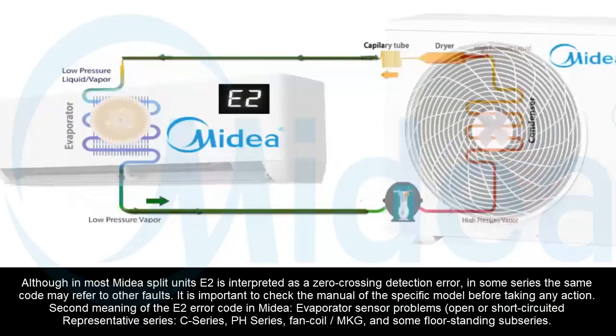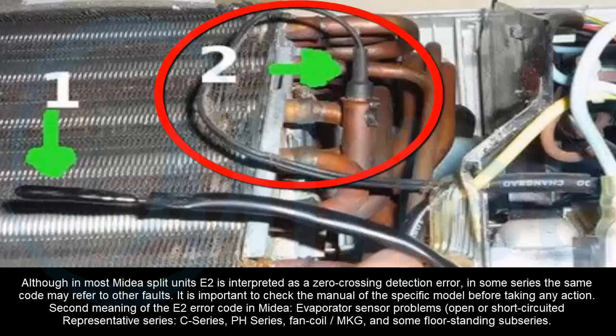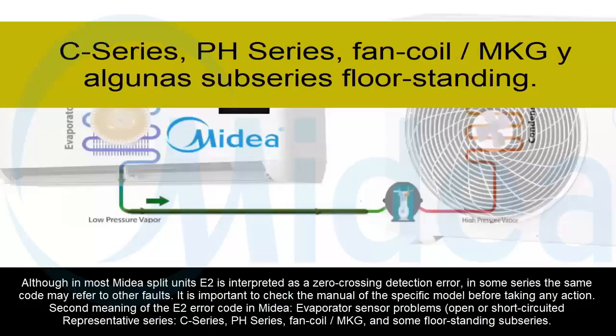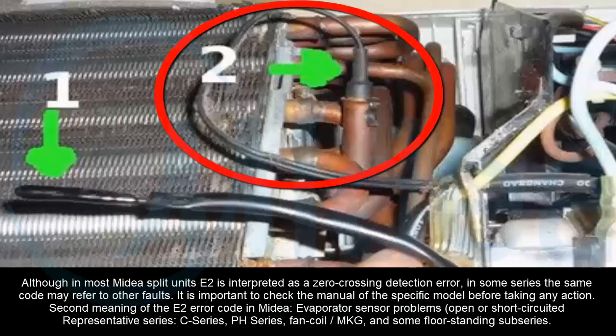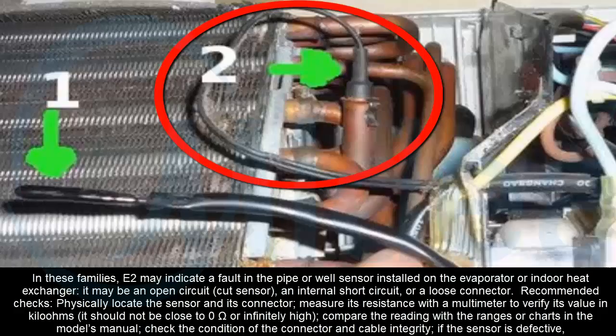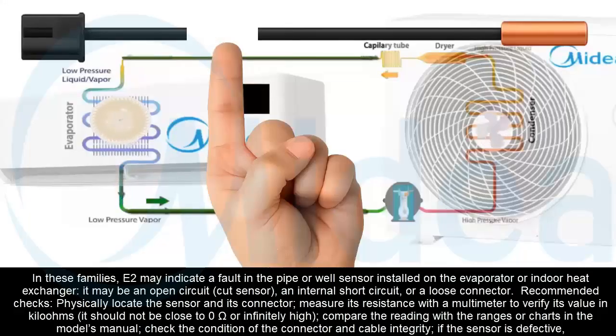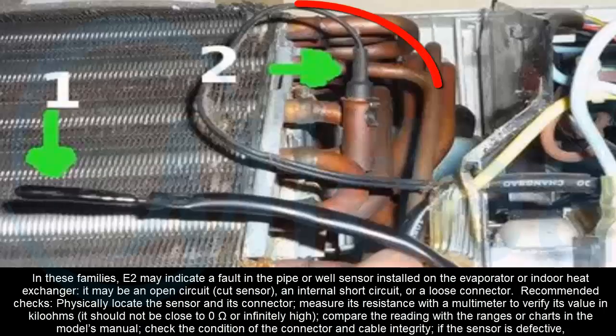Second meaning of the E2 error code in Midea: evaporator sensor problems, open or short-circuited. Representative series: C series, PH series, fan coil and some floor-standing subseries. In these families, E2 may indicate a fault in the pipe or coil sensor installed on the evaporator or indoor heat exchanger. It may be an open circuit or an internal short circuit or a loose connector.